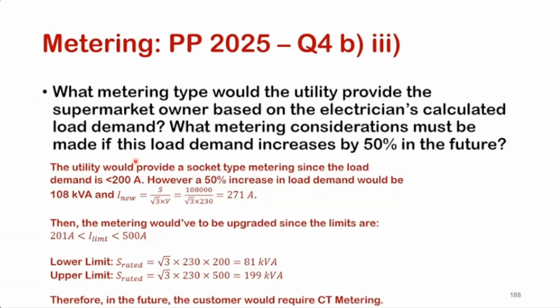We calculated the load demand before. It's 180 amps. But if the load increases by 50% in the future, that will be 1.5 times 72 kVA, which gives 108 kVA. And then your new current demand will be 271 amps. So it crosses the limit for socket type meter. So what are we going to do now?